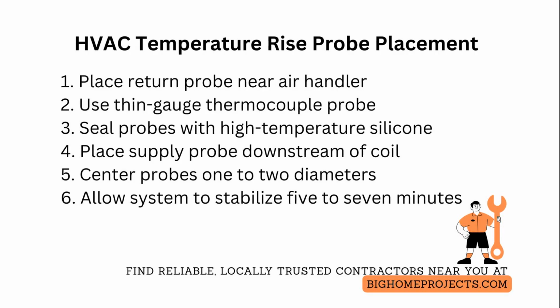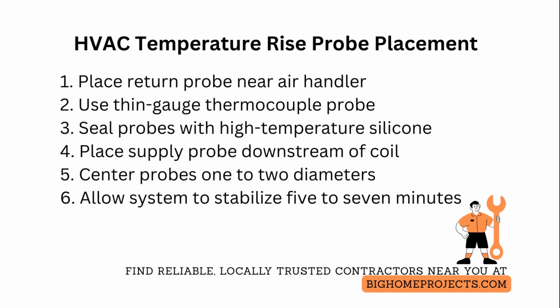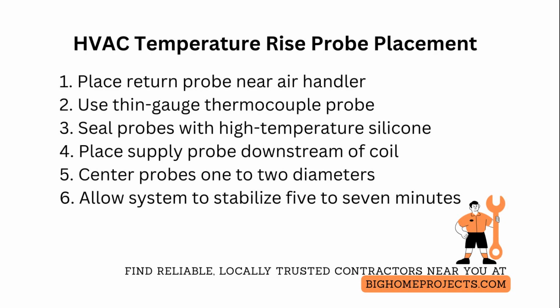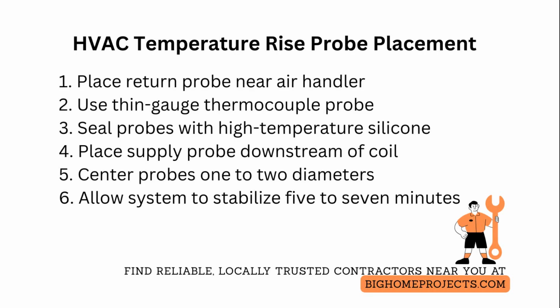If the measured temperature rise is outside the equipment rating, check probe placement, verify fan speed and filter condition, and confirm the equipment's heat input rating before calculating cubic feet per minute with the formula. Document probe locations, insertion depth, and sealing methods so subsequent tests are comparable and traceable.